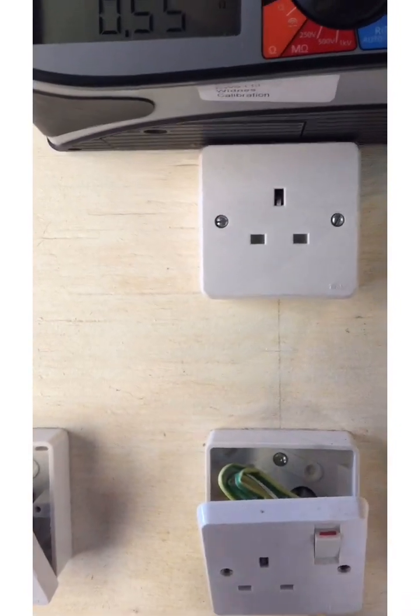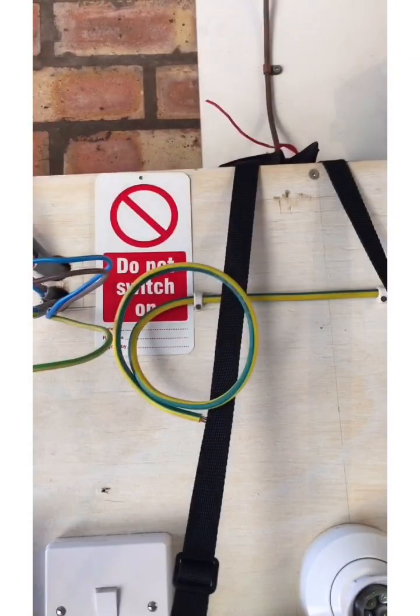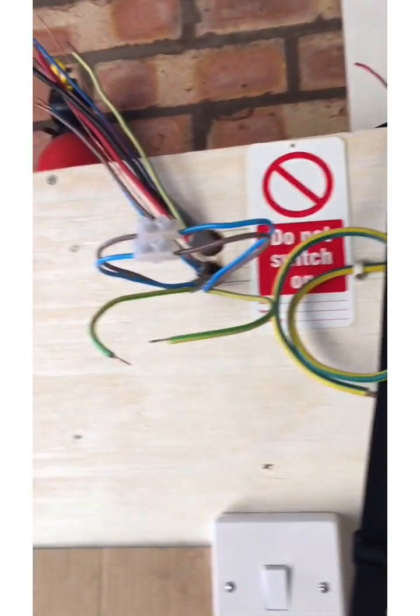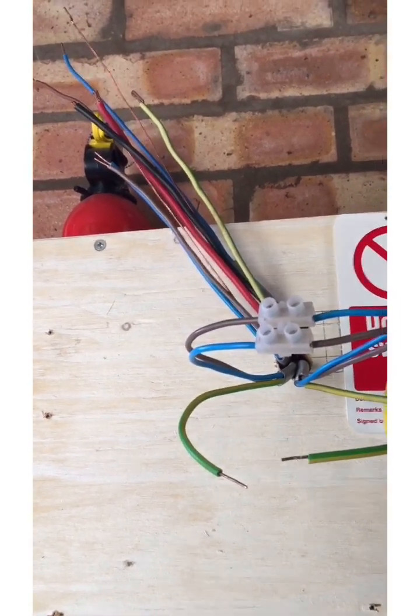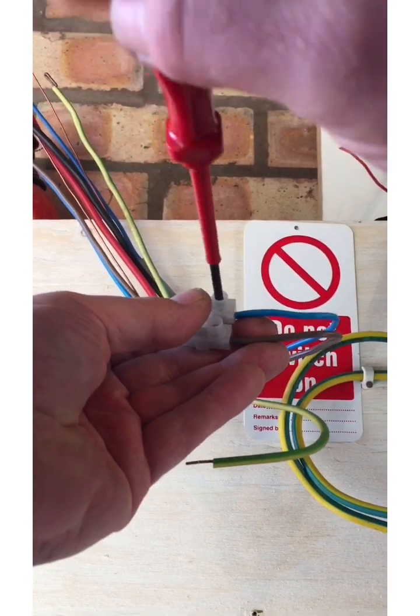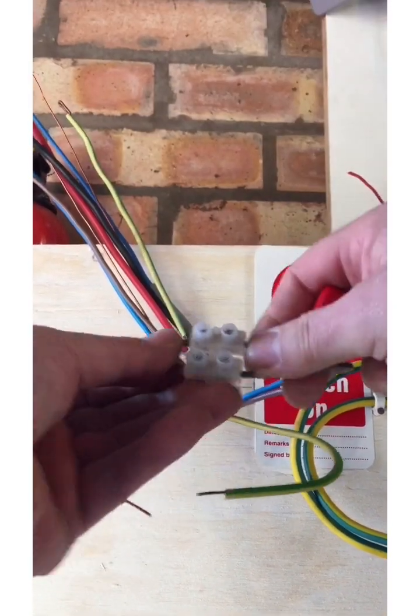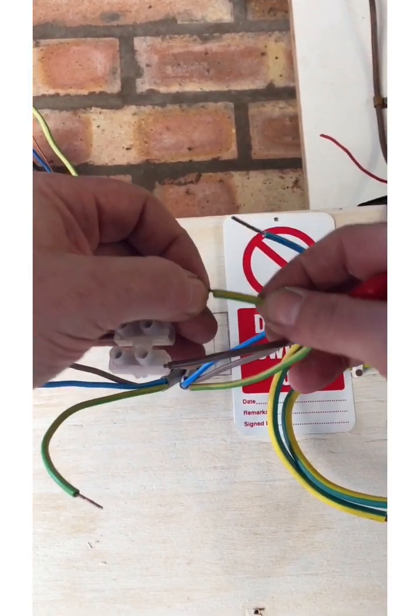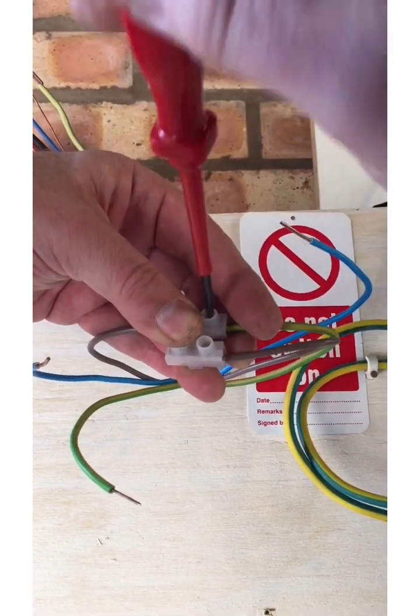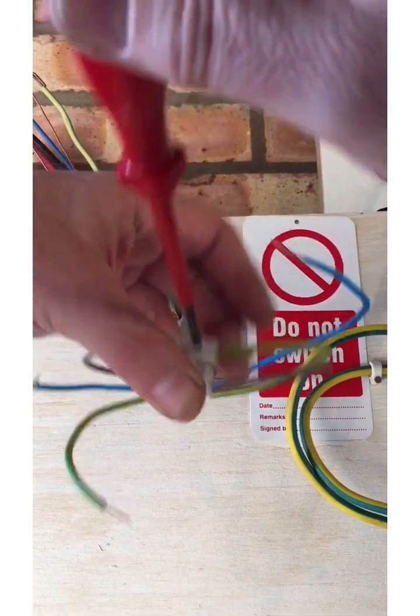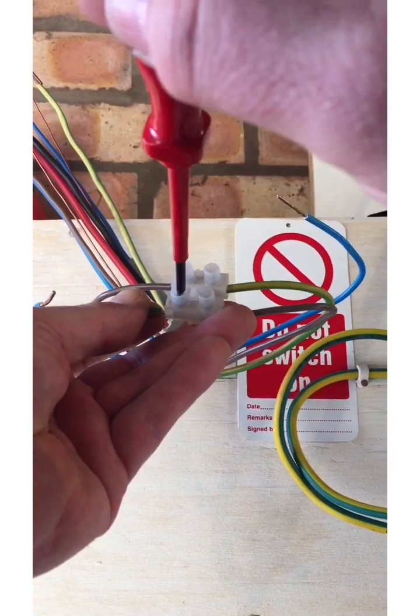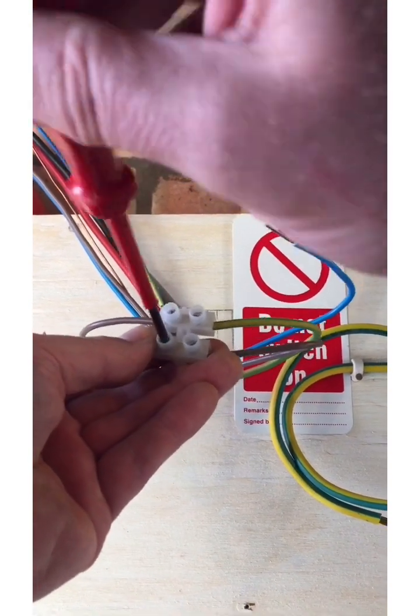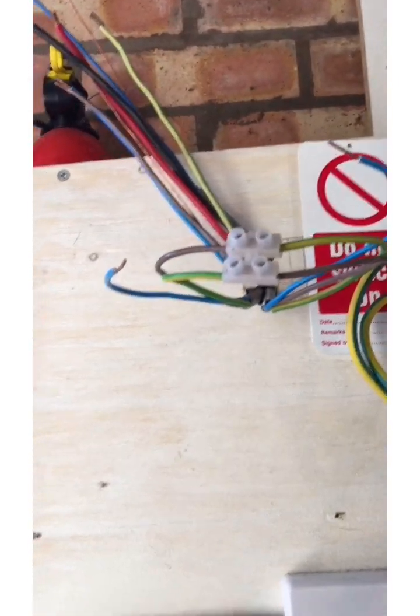So step three. Now step three is going to give us an R1 plus R2 value and it's also going to confirm polarity. And that's also going to be the final confirmation that the sockets are connected correctly. So if I take out the neutral and if I put the again outgoing line conductor incoming CPC and vice versa, and that's our figure of eight connection. There we go.